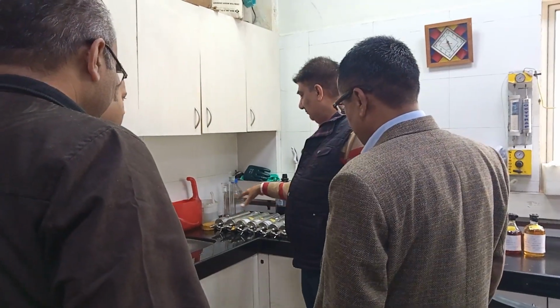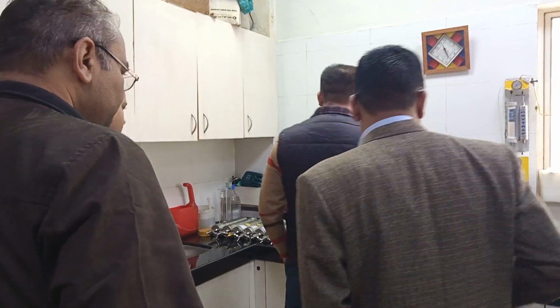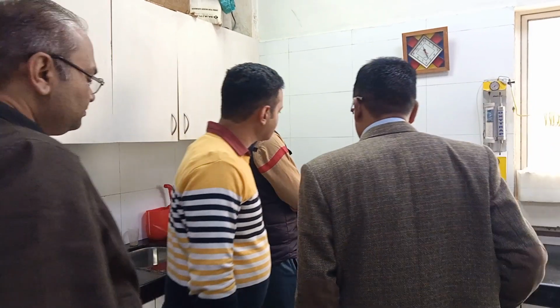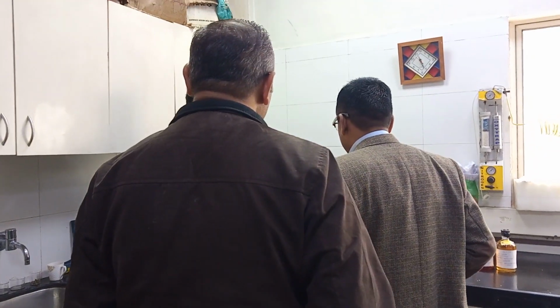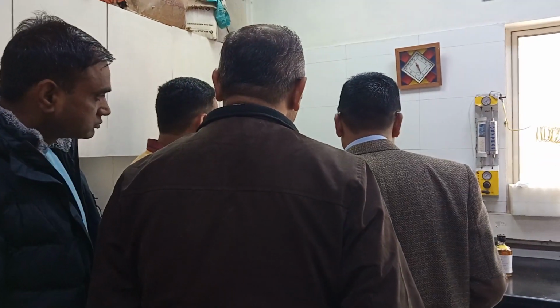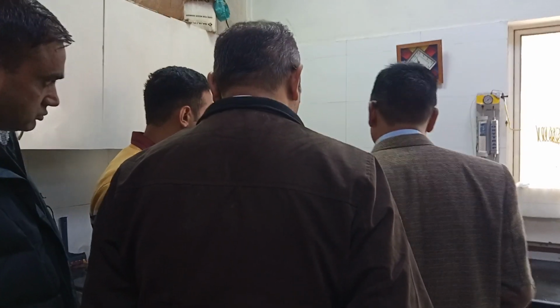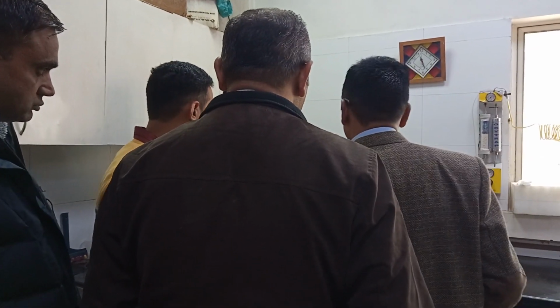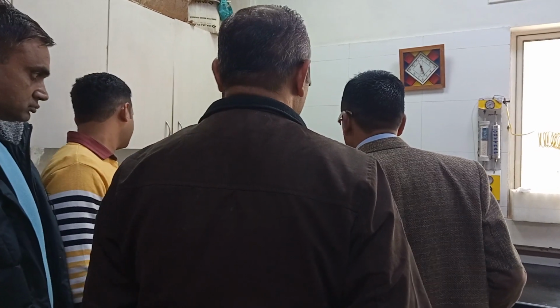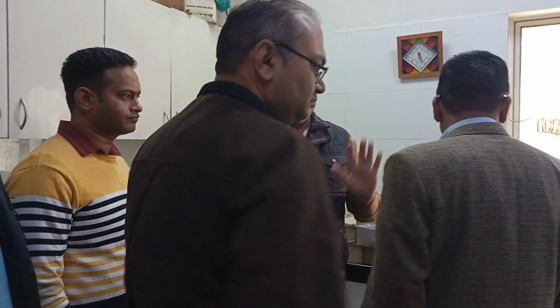DGA bottles are for the DGA testing of the transformers. These samples are coming to us, and sometimes the customer sends the samples in syringes also, like these lockable syringes. And these are all the bottles. This is the amber color glass bottle for routine parameter checking. So this is the sample preparation area. The remaining instruments are under calibration and have been sent. You have seen the vehicle yesterday or the day before yesterday.